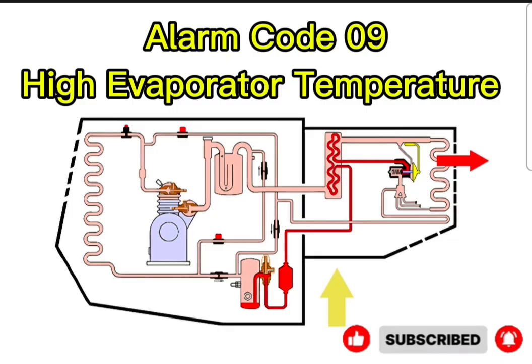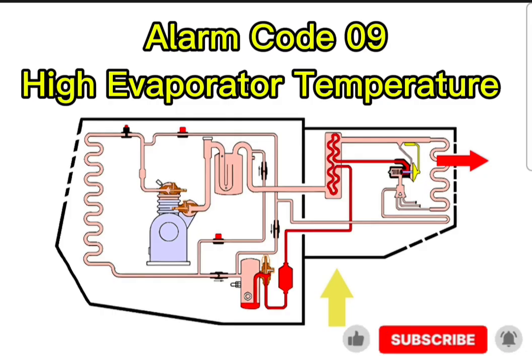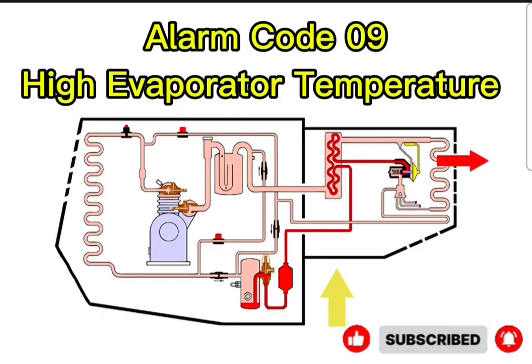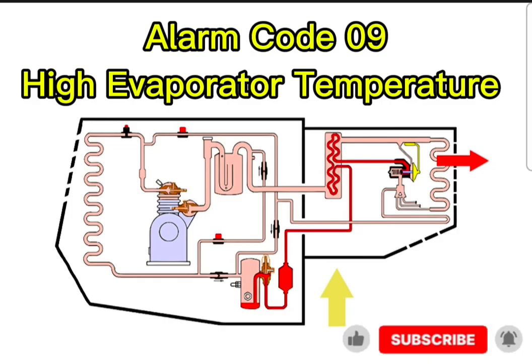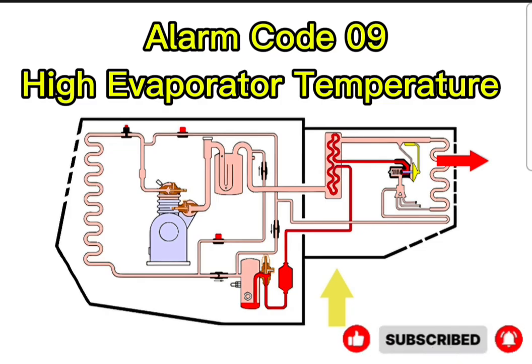And that explains why the system doesn't just take a break and try again in 10 minutes. The manual states very clearly in bold text, this alarm is cleared manually. Which is a huge detail. A human being has to physically go to the control panel, assess the situation, and press a button to allow the machine to turn back on. Because the machine locks itself out. It cannot trust its own automated recovery protocols anymore.